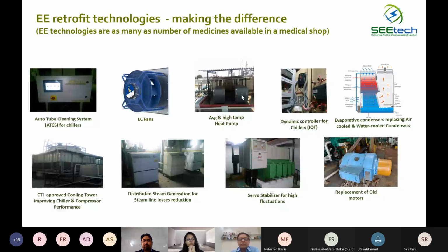One is that you save on the thermal fuel, and with the diesel cost going so high, the savings are phenomenal through the heat pump. But instead of making it air source, you make it water source. So whatever the resultant saving, that gives you additional saving on the chiller side. Your actual chiller operates on a lesser load, and when you reduce the loading on your chiller, your performance also improves.